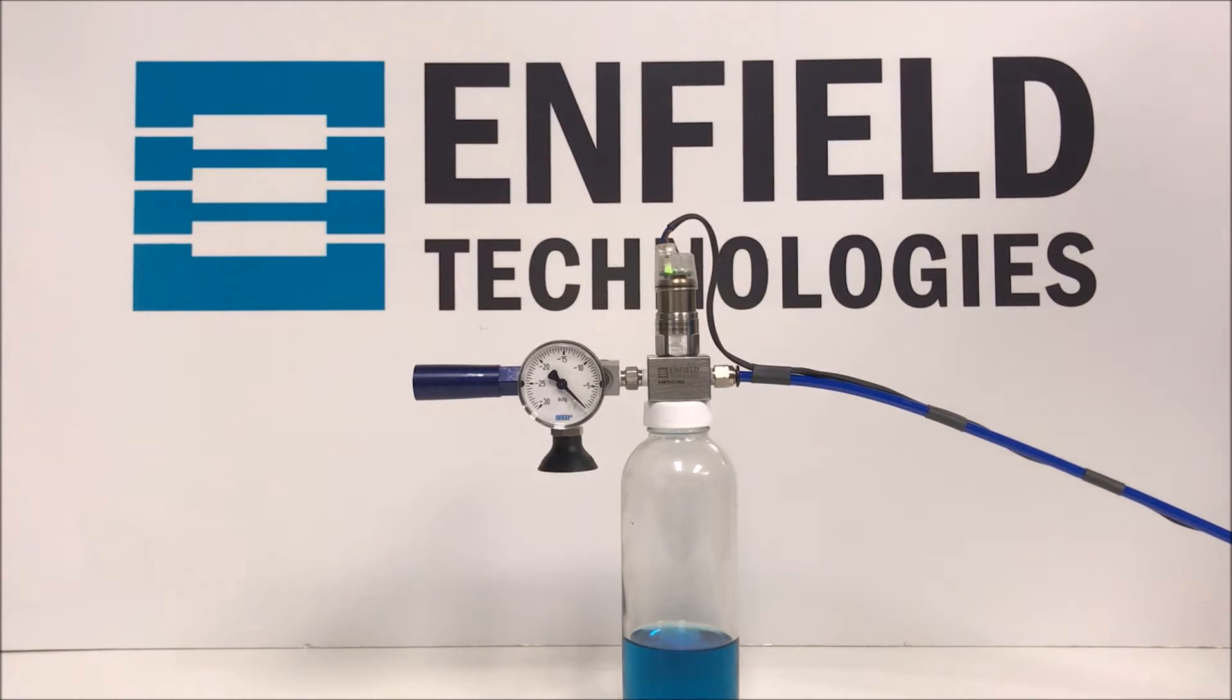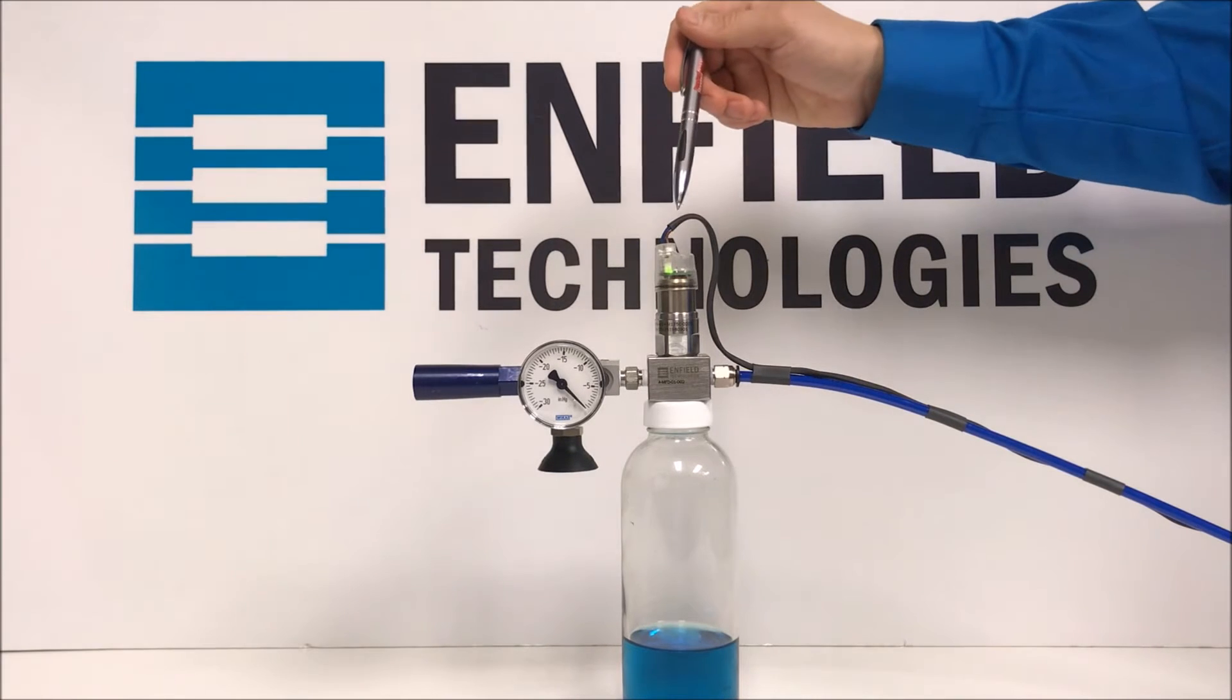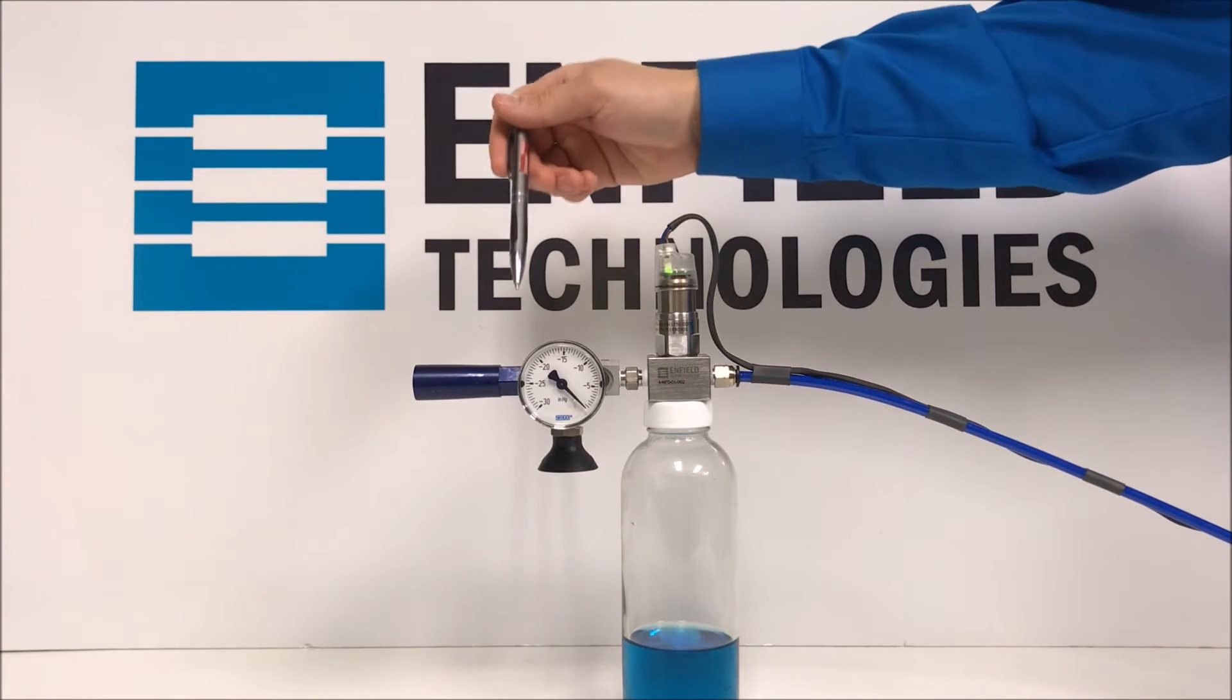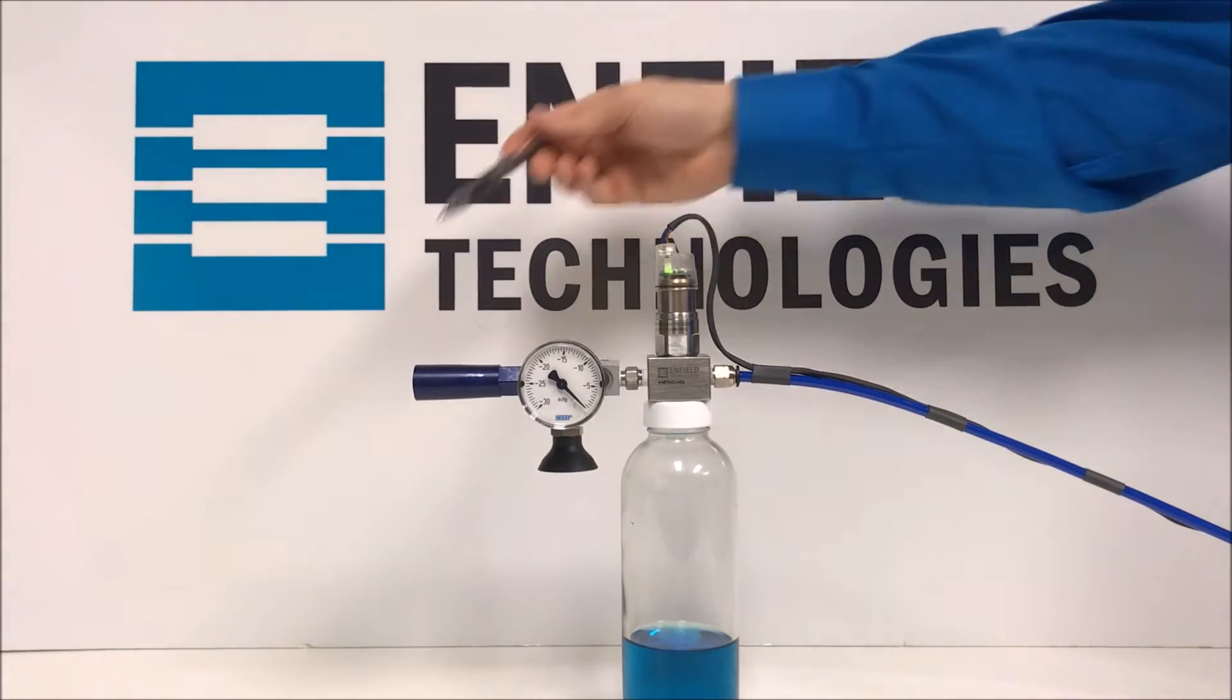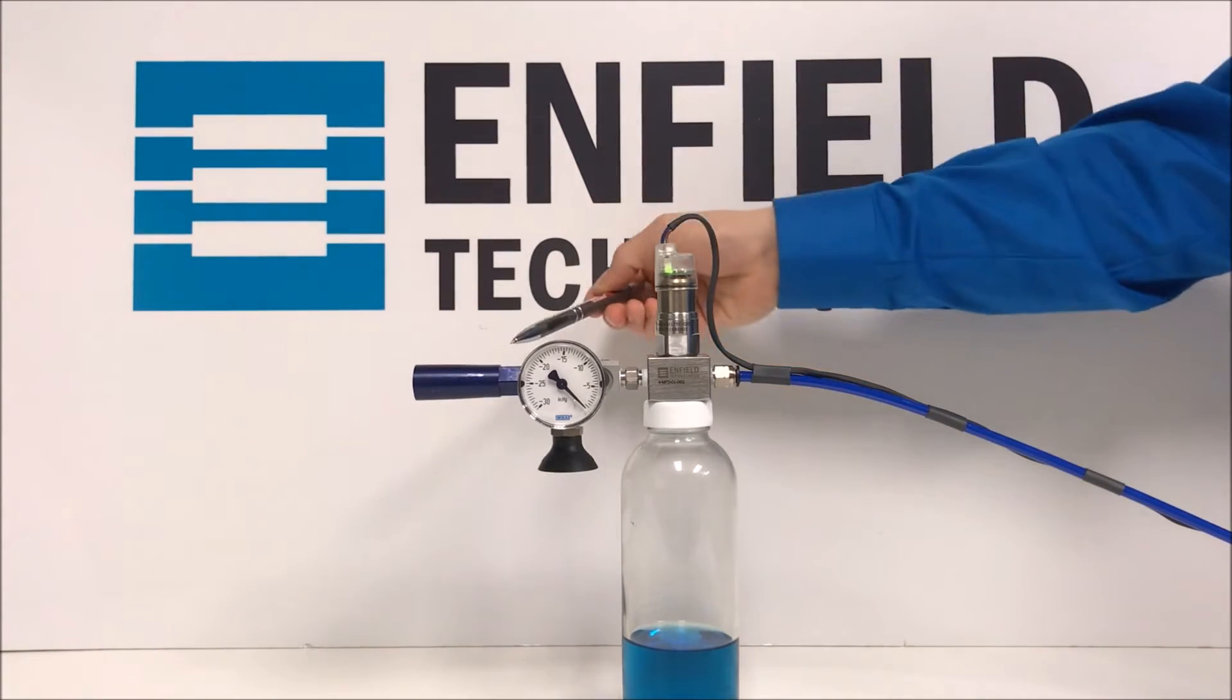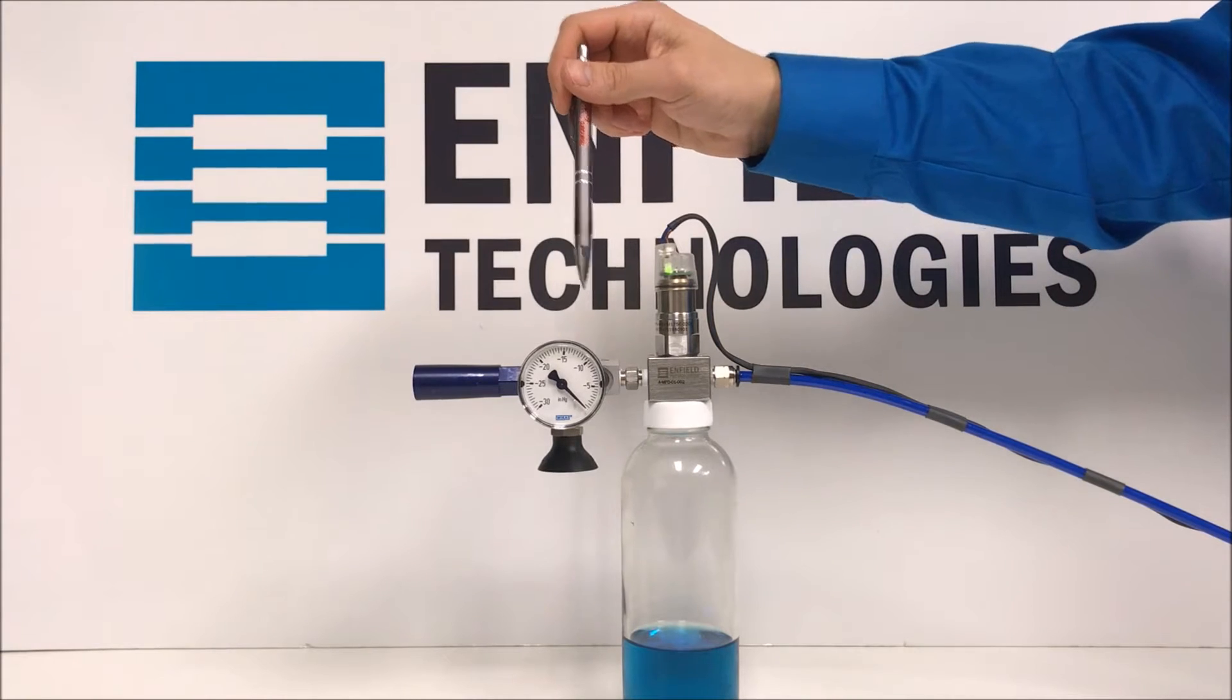Our setup consists of the Enfield PFE proportional valve combined with a Schmalz EcoPump vacuum ejector. The basic principle of the vacuum ejector is the more air that goes through it, the higher the vacuum level it generates at the suction cup.